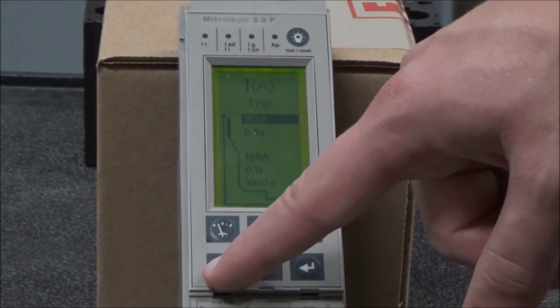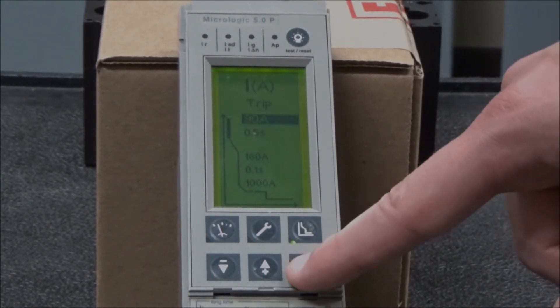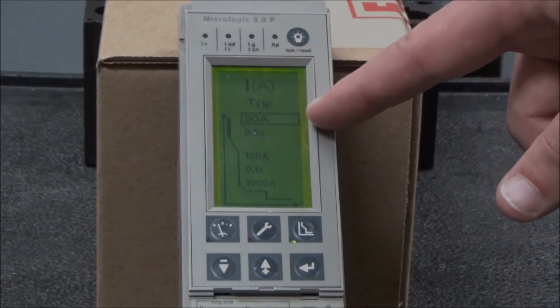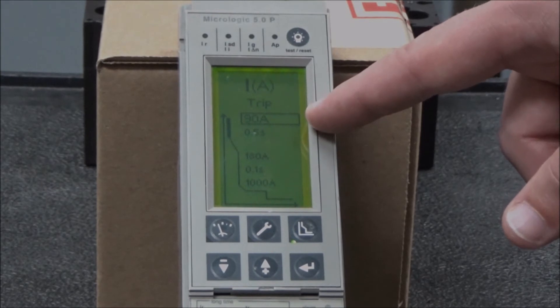Once you get to the desired amperage, you will hit the select again to save it. The long time amperage setting can be adjusted in 1 amp increments.